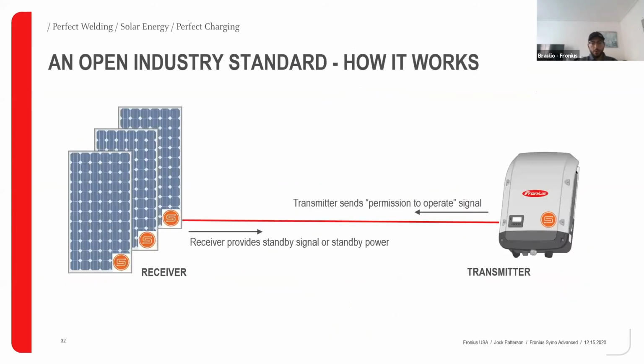It's fairly simple how it works. As modules and inverters are connected via DC wires, power line communication can easily be utilized in the solar system. If modules have a Sunspec receiver and the inverter has a Sunspec transmitter, they can communicate with each other. The receiver provides a standby signal and the transmitter sends a permission signal. If AC power or the inverter is turned off, the permission-to-operate signal goes away and the receiver in the module shuts the module off. It's as simple as that—very plug and play.